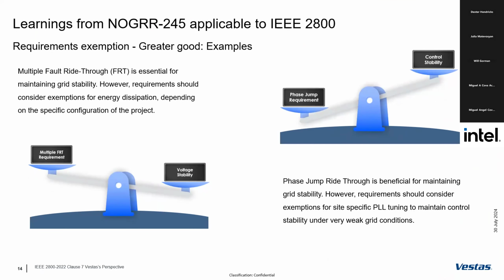So these two are very good examples that sometimes the greater good is necessary, and there might be cases where we need exemptions. We might need to reduce, in some cases, the multiple FRT number that we can ride through, as long as we can recover voltage in a stable manner. But we might not evaluate that same plant in the same way.